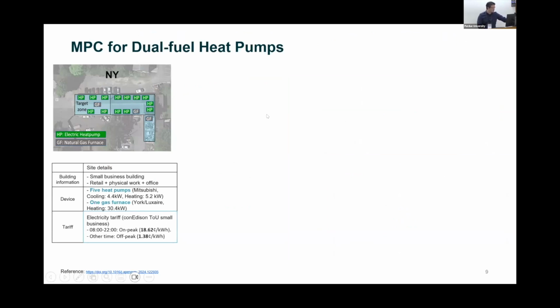This is another system. So far, we just talked about the ACs, but this is the extension to a heat pump and dual fuel heat pump system. In this case, we have a heat pump, and also gas furnaces combined. It's a dual fuel heat pump system. It's not a packaged dual fuel heat pump system, but in the market, especially commercial buildings, although they want to electrify their system, they don't want to get rid of existing gas furnaces. That naturally makes dual fuel heat pump systems.